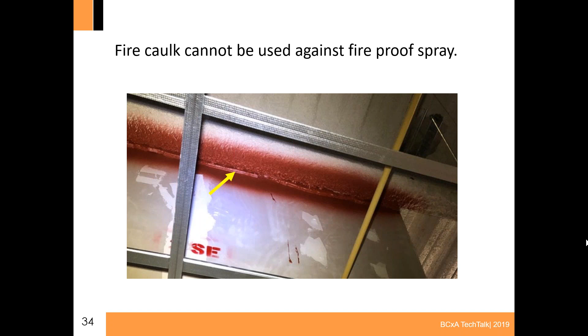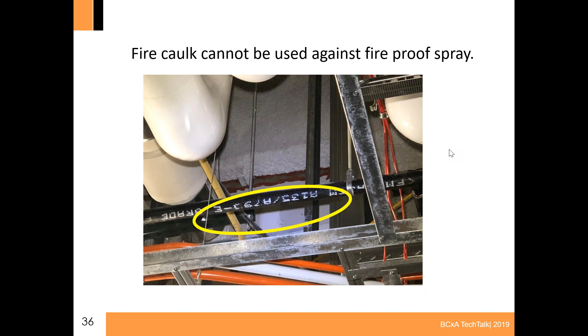Here's another example of something similar. We're not talking about the ASTM number on the sprinkler pipe, but up there with the mineral wool, again attached to the fireproofing on the steel beam — that's another inappropriate use of fire caulk. It should have just used fire spray with no fire caulk.